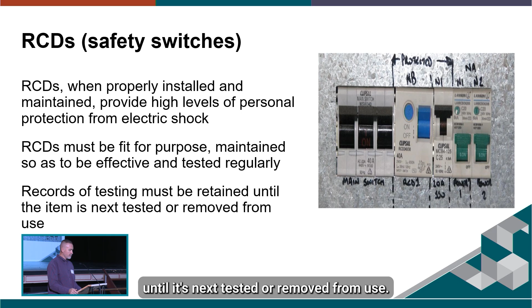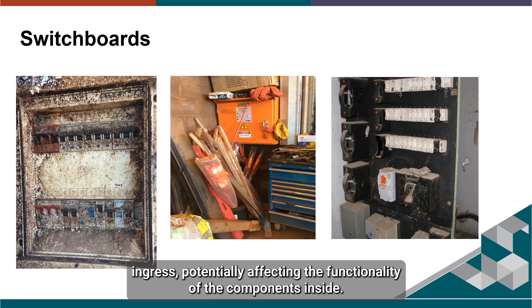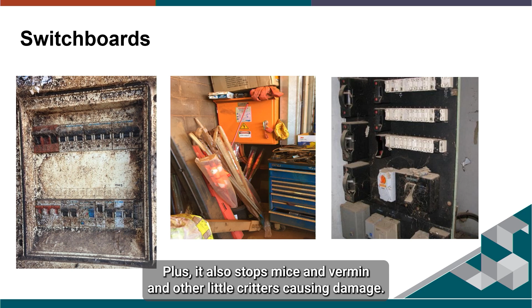Switchboards. Electrical switchboards do require maintenance. Keeping them clean can not only ensure they function correctly, but also keeps them safe. They should have a lid or a door that's lockable, and inside the escutcheon covers and panels should be secured properly so that there's no gaps where a finger could fit in. This will stop any inadvertent contact with the live wires inside and stops dust, dirt, and moisture ingress, potentially affecting the functionality of the components inside. Plus, it also stops mice and vermin and other little critters causing damage.